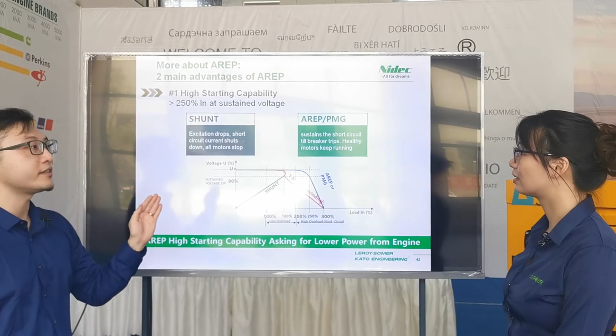Also for short circuit capability: the AVR of shunt gets power from the alternator terminal directly, so if a short circuit happens, the machine with shunt will shut down directly. But the machine with AREP and PMG can meet like a 300% rated current for 10 seconds for selective protection of the machine. So normally such capability is necessary for parallel application, and also for some special applications.